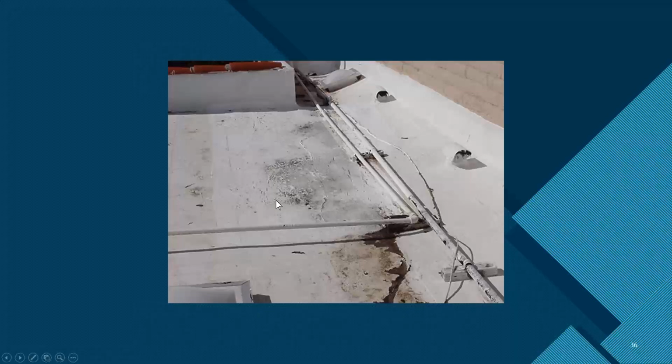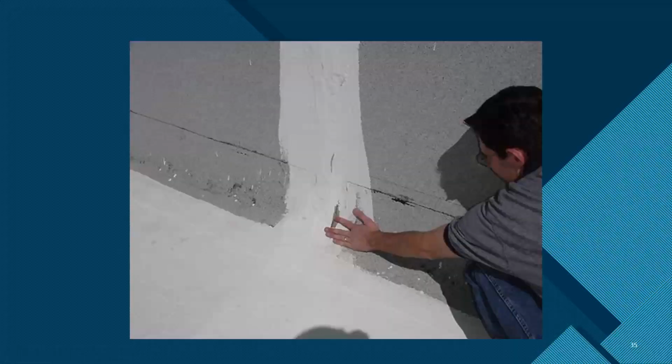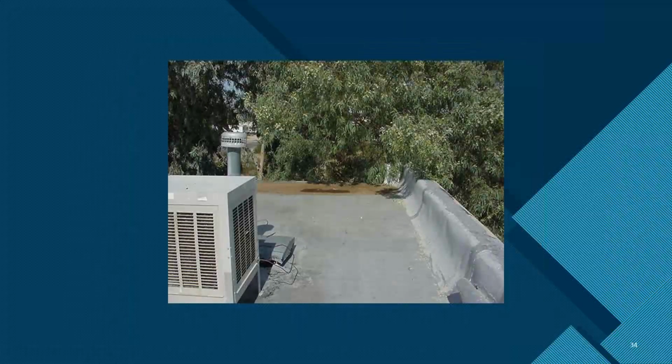Isn't that gas vent too close to that swamp cooler? Yeah, the problem here is that this gas vent's been extended in height, so it's higher. It's got to be a foot higher or more than this. And then here's your combustion air vent. But there's not much you can do about it because it comes up out of the roof.